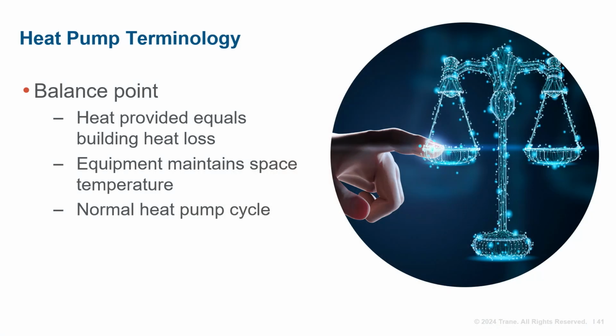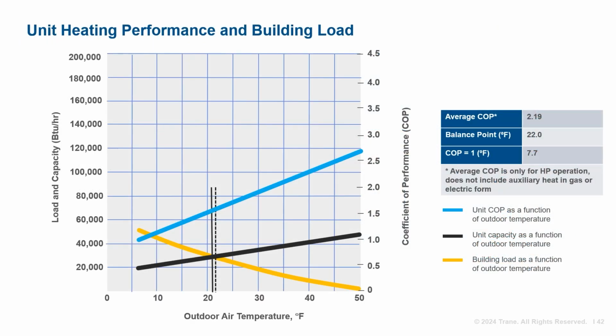Thanks, Eric. In this segment, we'll review some common heat pump and dual fuel terminology. The balance point occurs when the heat pump can provide exactly as much heat as the building heat loss is resisting. At this point, the equipment will maintain the space temperature by running continuously. Above this point, the heat pump will cycle normally. The attached image represents the difference in the building load as a function of outdoor air temperature versus a typical unit's capacity. The vertical indicator, along with the intersecting variables, represents the balance point.